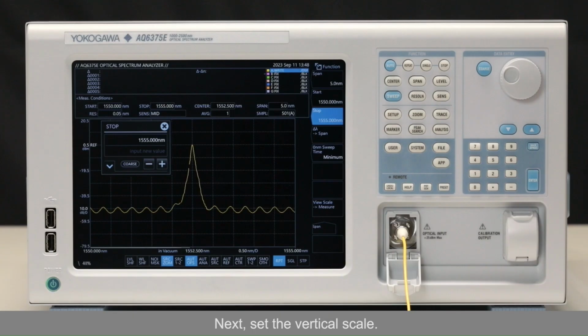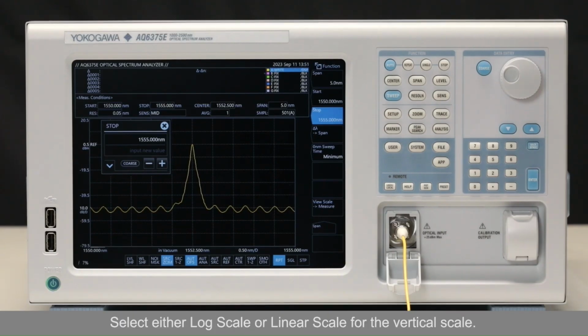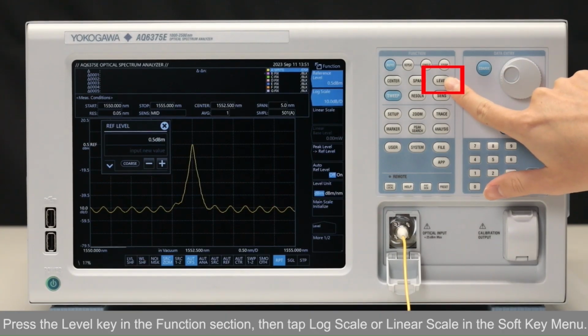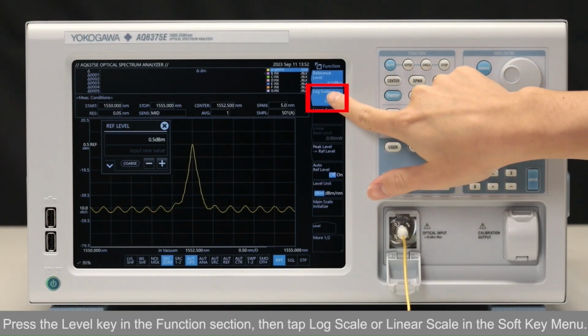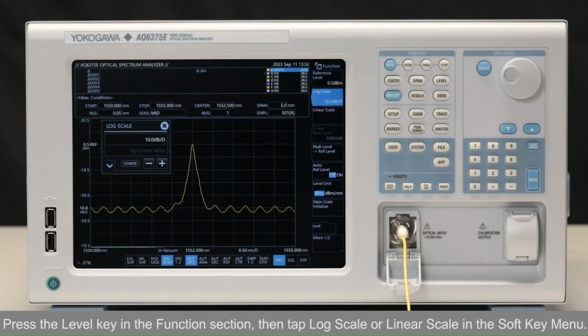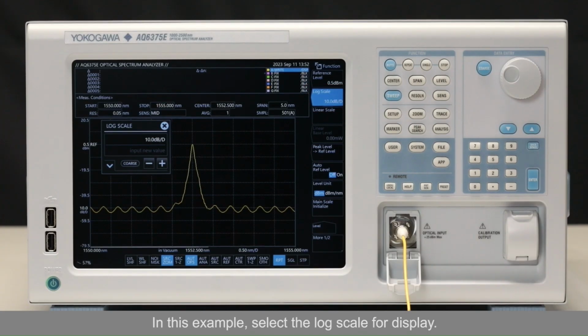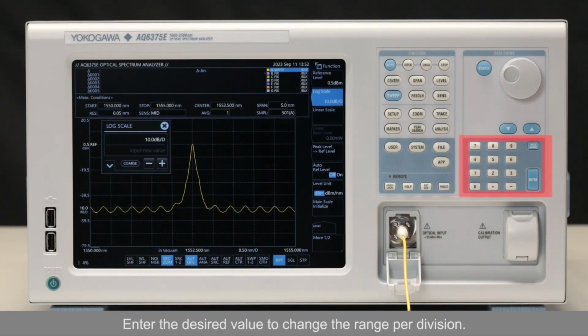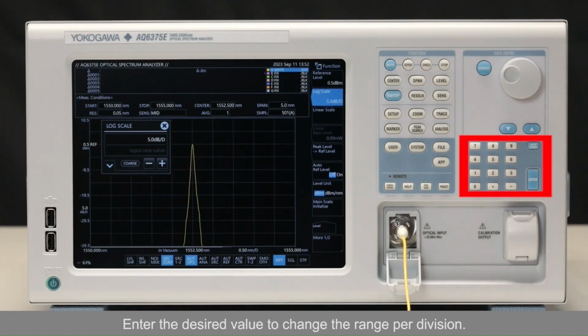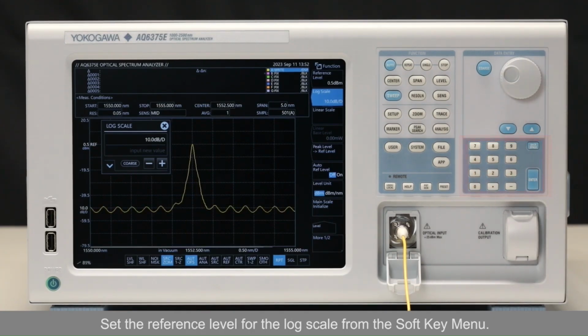Next, set the vertical scale. Select either log scale or linear scale. Press the level button, then tap log scale or linear scale in the soft key menu. In this example, select the log scale for display. Enter the desired value to change the range per division. Set the reference level for the log scale from the soft key menu.